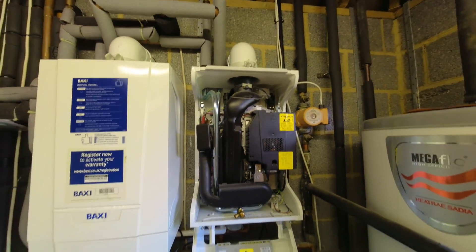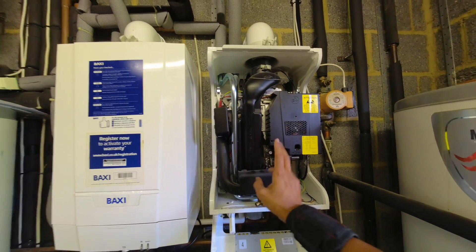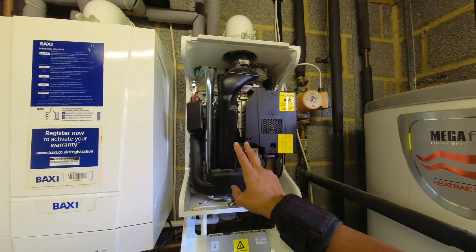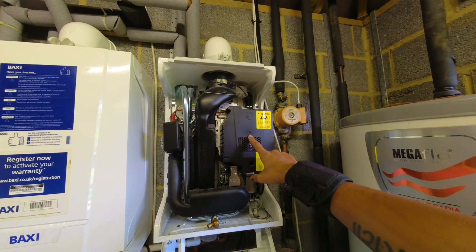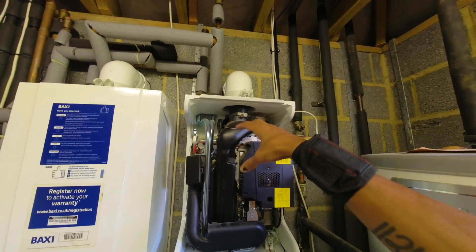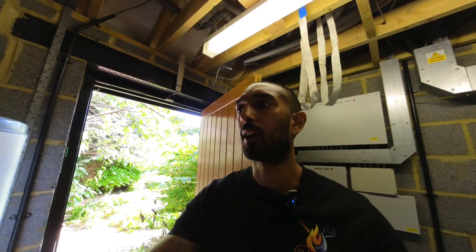It's been a little while since I've stripped one of these out, so I'm going to go through it step by step again. You've got two silencers on here — or snorkels, flue collectors, various different names for them. You need to take both of those off, and then you basically need to remove the gas valve, the fan assembly, and the PCB — all in one go as a single unit called the combustion control unit.